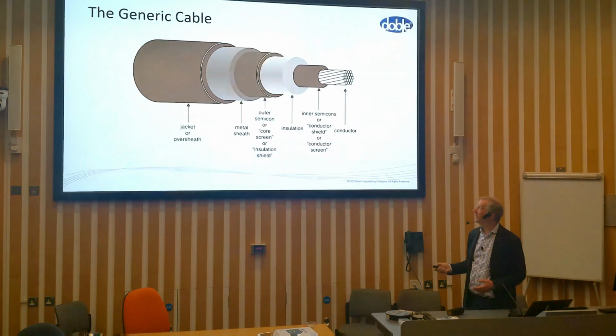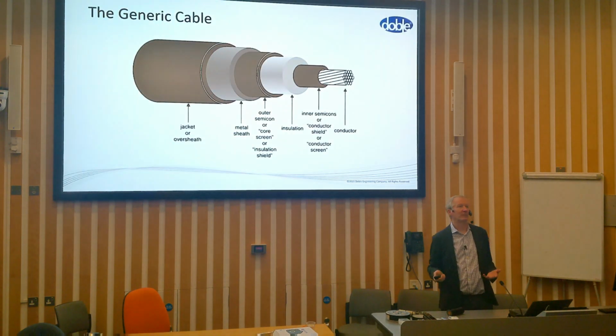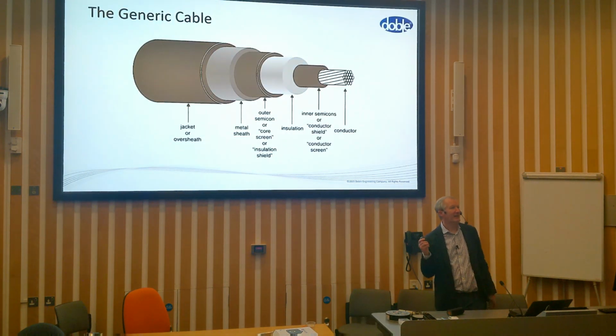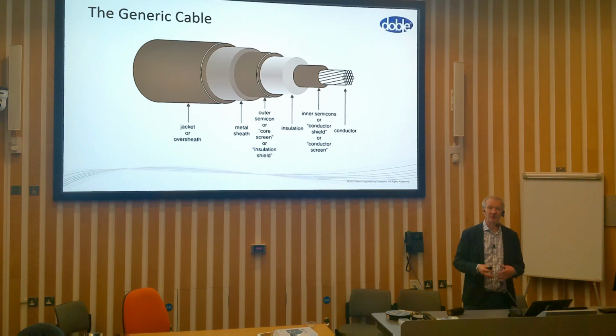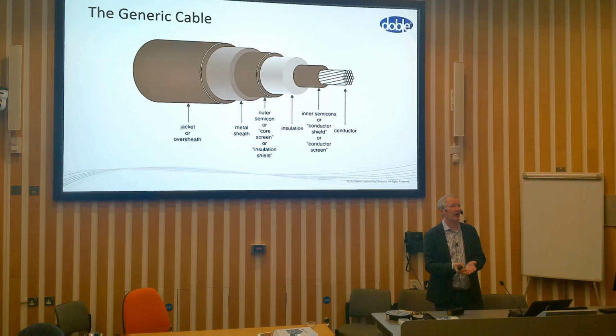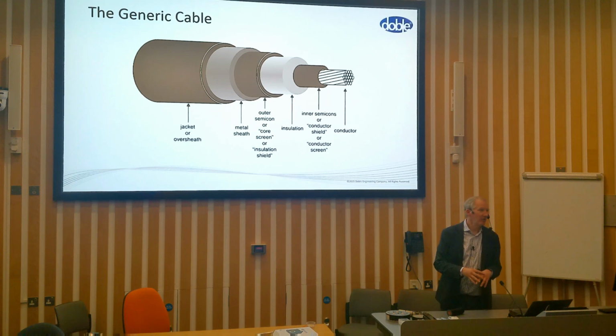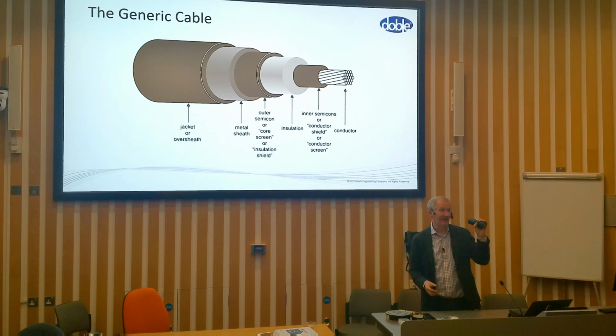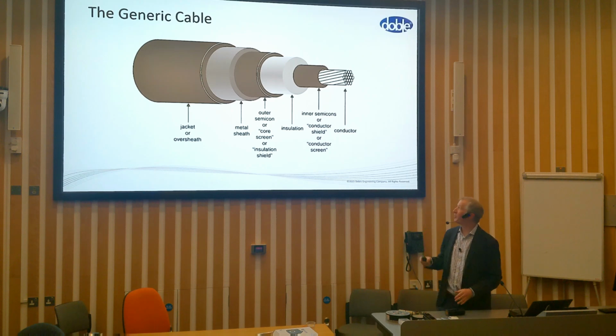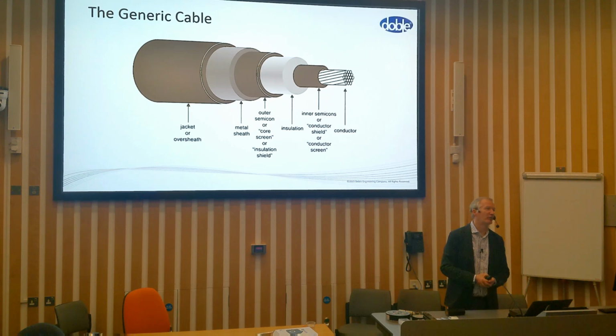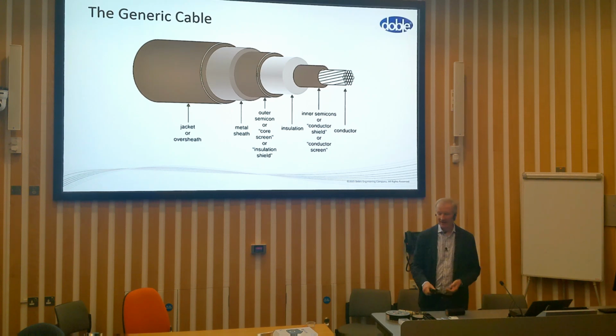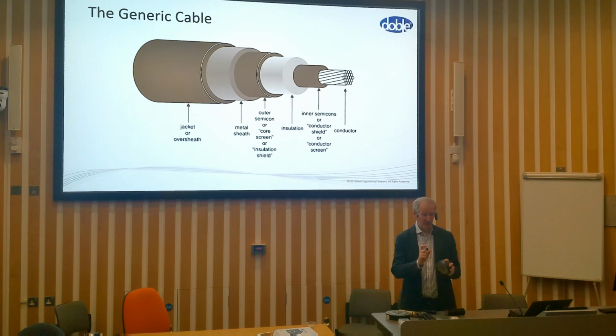So a lot of variety, but generally they all come down to this: a piece of metal in the middle to carry the current, some kind of insulation around it, and then some kind of containment, either to keep the oil in, or in the case of these XLP cables, to keep the water out. Then some kind of protection on the outside, the oversheath, which these days is normally polythene.